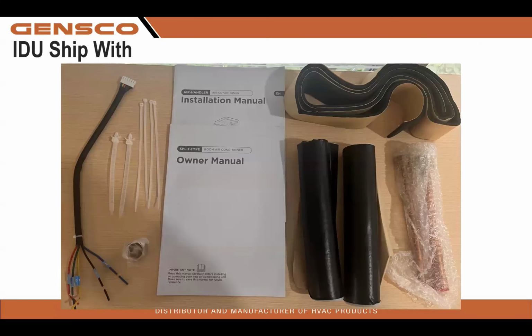This is all a part of the installation kit, the installation manual, the owner's manual. This is the pigtail that plugs right into the board for our 24-volt comm mode. If we're not going to run fully communicating, this just plugs right into the board. You'll see our R, G, Y, O, W. We've got some zip ties right there, a little bit of extra insulation and some foam tape.